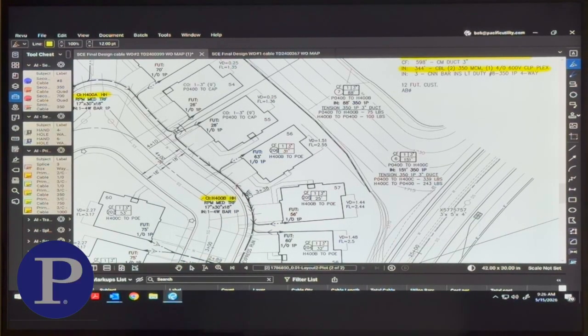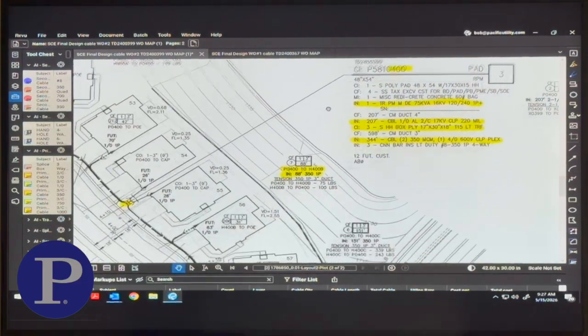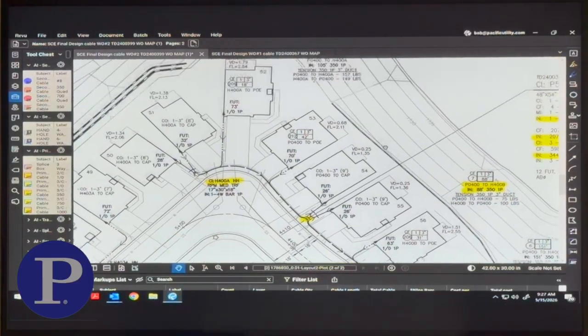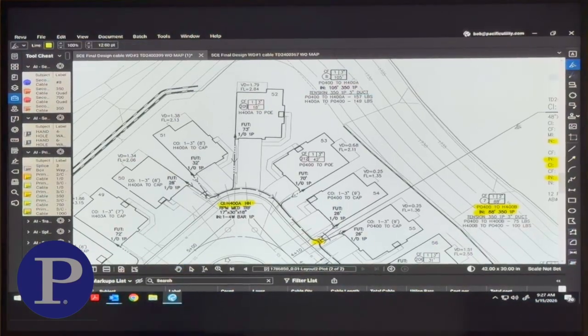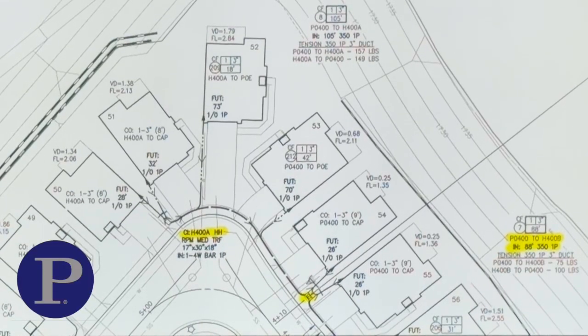Those cable callouts, so we're going to be pulling cable from here to this handhole right here, and this is the callout right here. 88 feet, 350 single phase. That's the pad number, P0400, to handhole 400B, and then transformer 400. And then if you look up here, same thing. Let me stop here. Transformer to handhole. Handhole A, we're going transformer 400 to handhole 400A, 105 feet. That's your cable callout. So we're pulling from here to here.